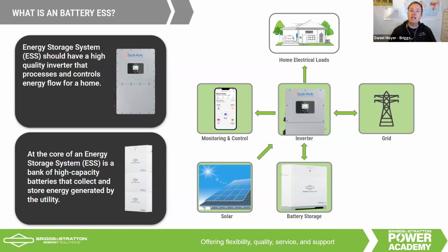It also allows us to scale energy and power separately. What I mean is, if the inverter, charger, and battery are integral, then in order to increase storage capacity you have to add more batteries that include that inverter charger — you're scaling them up together. What we can do instead is, if you need more energy or backup time, you just add more batteries, and if you need more power, you just add more inverters, like that Sol-Ark.